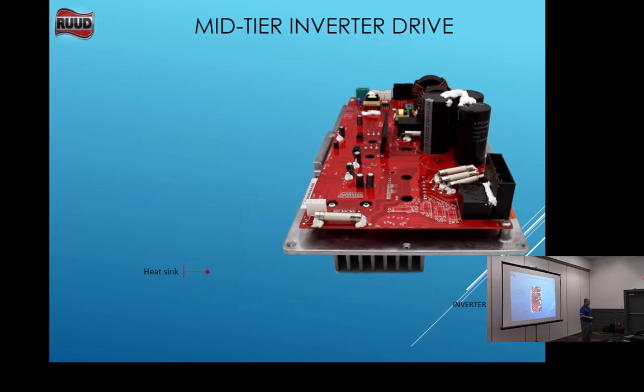The heat sink on the back of this inverter drive gets hot. So it's got a heat sink on the back of it. Dirt daubers like to live here. So if you're doing maintenance and you're washing the inside of that unit out, you can wash the back. It's got a gasket. It's not going to get water in here. Make sure you clean that out also. If you get high inverter temps, that might be something to look at.